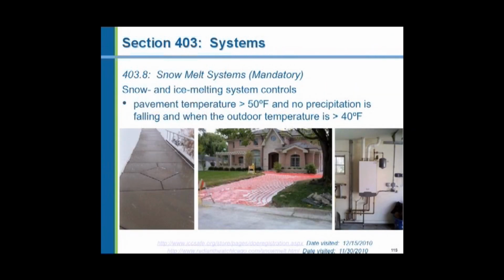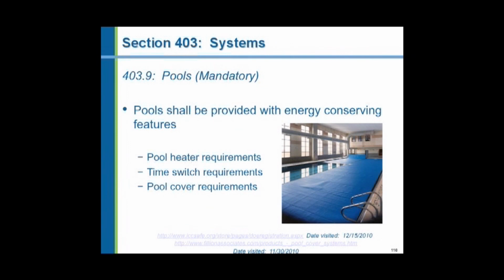Snow melting systems. The code says that if the pavement temperature is above 50 degrees and the outdoor temperature is above 40 degrees and it's not snowing, shut it off. Only when it's cold and snowing. So we have to have some sensors, not only temperature sensors, but moisture sensors, to shut off the snow melting systems when they're not required. Swimming pools have to have an energy conserving cover, a pool blanket. There are some additional requirements. The pool heater cannot have a standing pilot light.